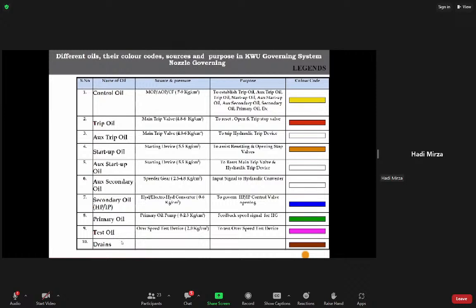We'll see what the purpose of this control oil is. Control oil is to establish trip oil and auxiliary trip oil. Basically, all the oils are generated from control oil only. In the medium pressure governor, that is 600 megawatt, we have 8 bar and 32 bar basically. Control oil is around 32 bar, and 8 bar is for the governing system. Servo valves operate at around 32 bar, and for governing it is around 8 bar. Trip oil is to reset, open, and close stop valves. Auxiliary trip oil is for hydraulic trip devices like the overspeed trip device. We don't have the vacuum trip device in 600 megawatt.